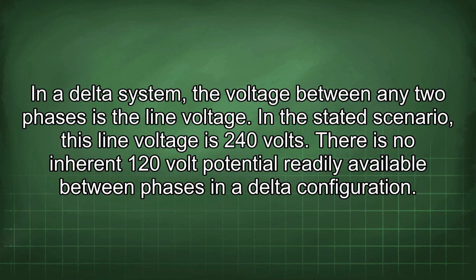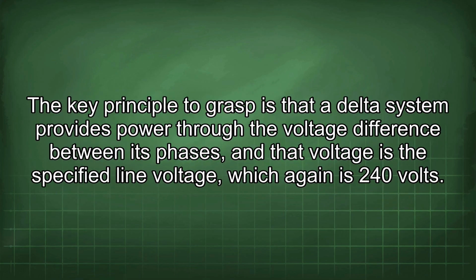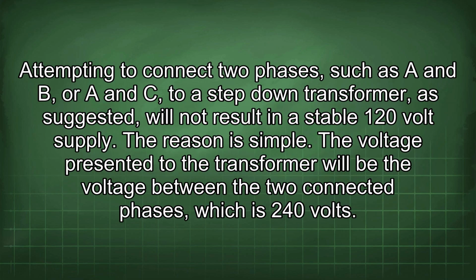There is no inherent 120 volt potential readily available between phases in a delta configuration. The key principle to grasp is that a delta system provides power through the voltage difference between its phases, and that voltage is the specified line voltage, which again is 240 volts. Attempting to connect two phases, such as A and B, or A and C, to a step-down transformer, as suggested, will not result in a stable 120 volt supply.